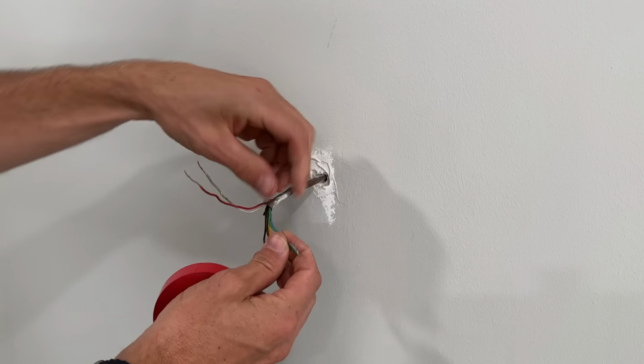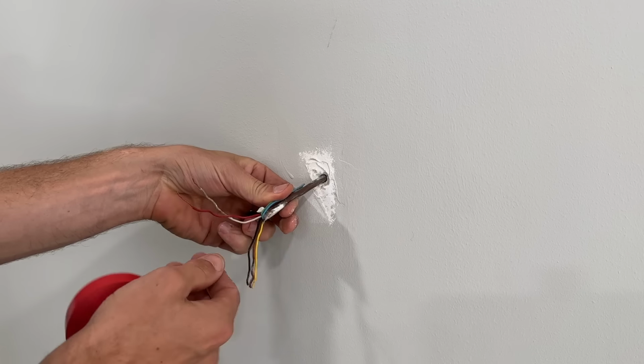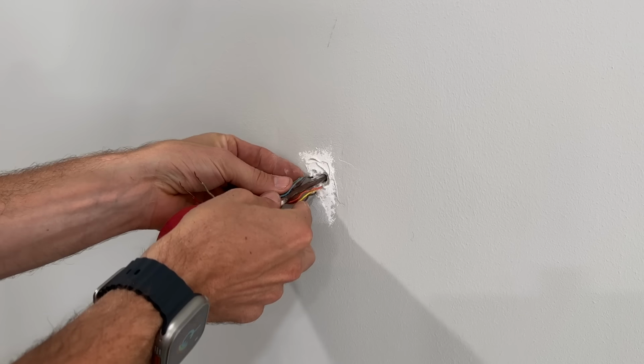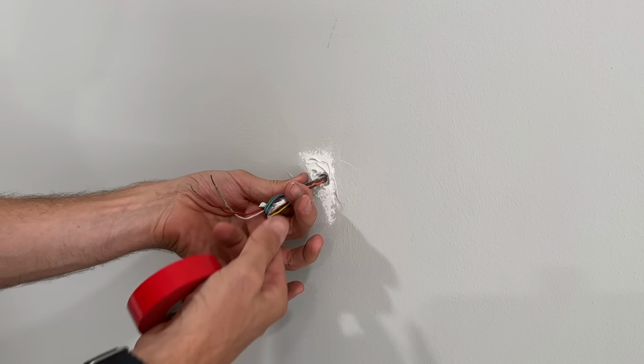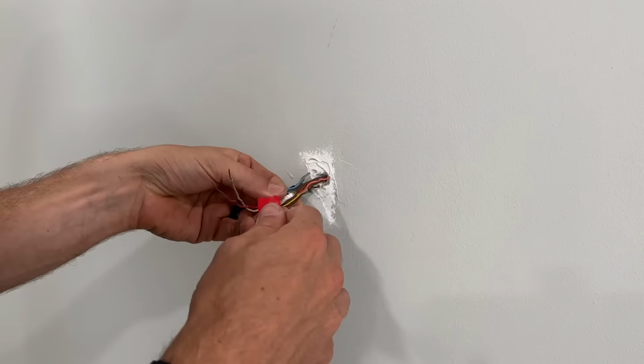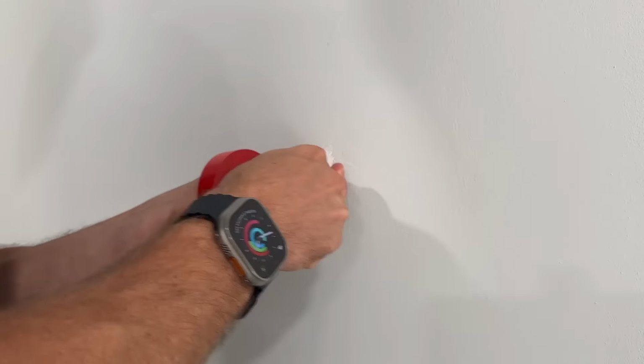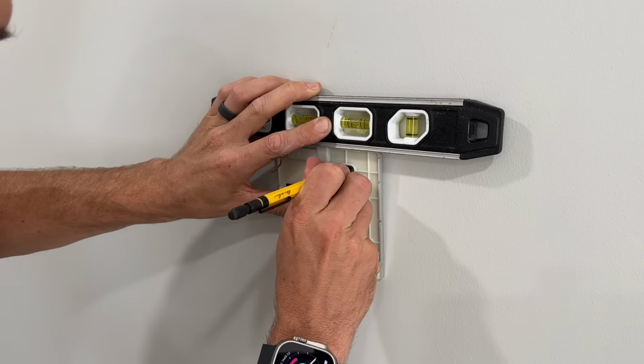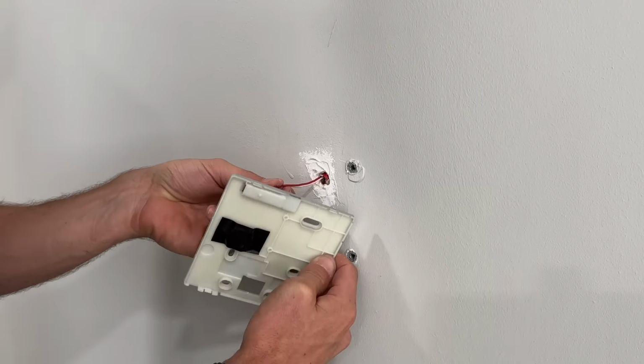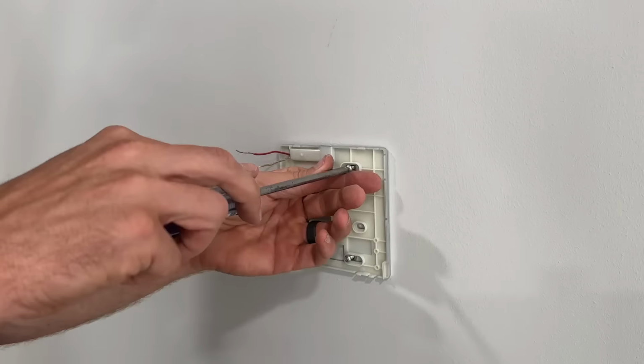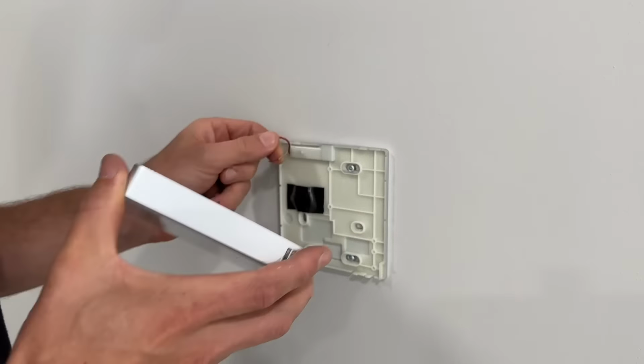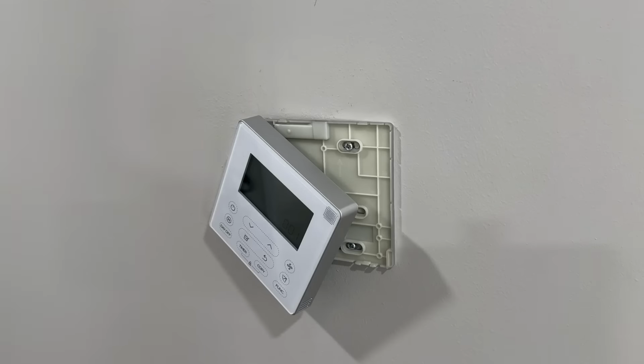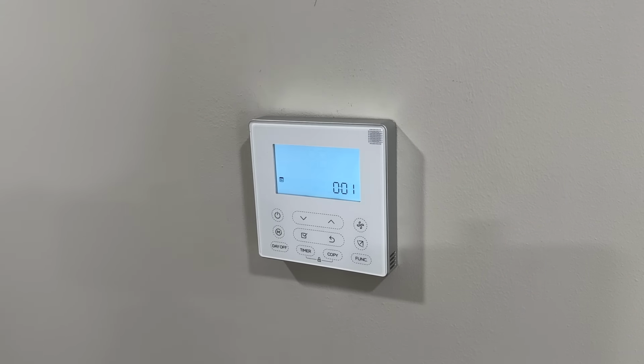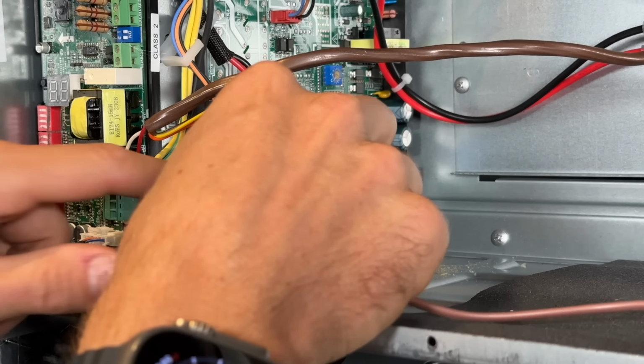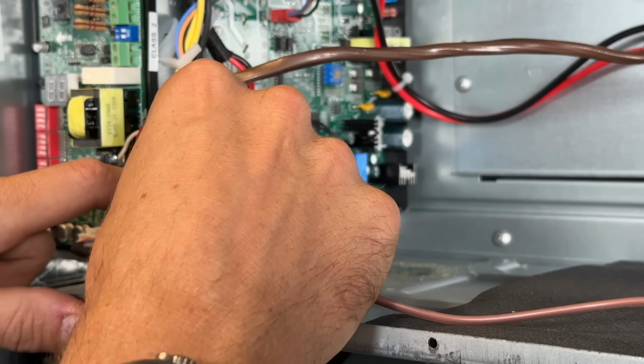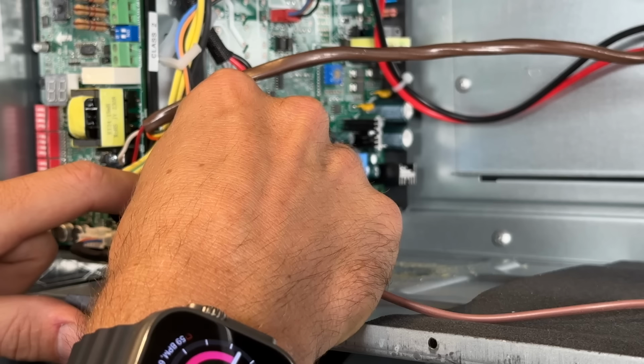I do want to keep the rest of these wires in place, so I am just going to double them back, spread them around the outside of the wire and then tuck this back into the wall so we only have the 2 wires coming out into the base of our thermostat. And then for the 2 thermostat wires that will go out to our outdoor unit, white will be going into S1 and red will be going into S2.